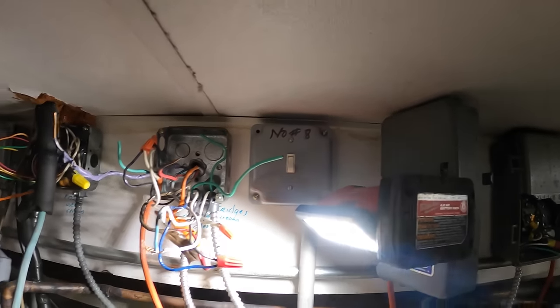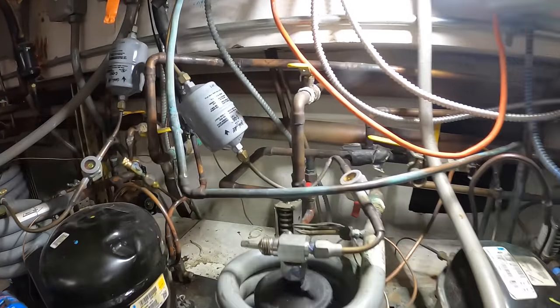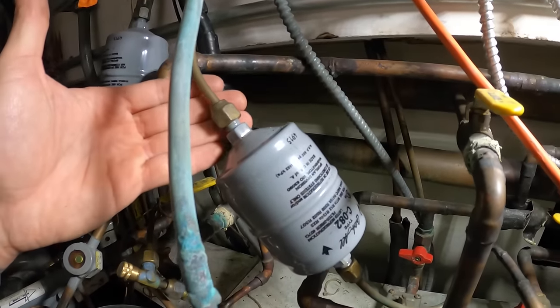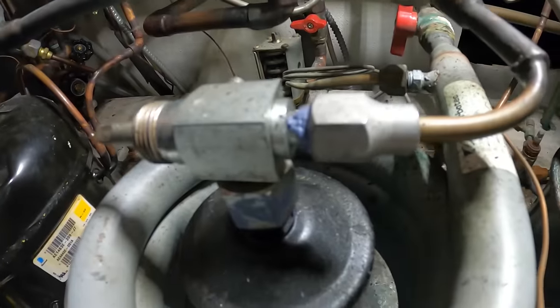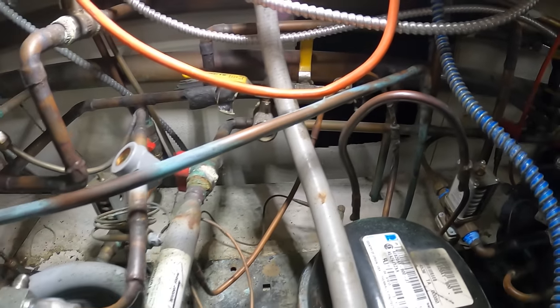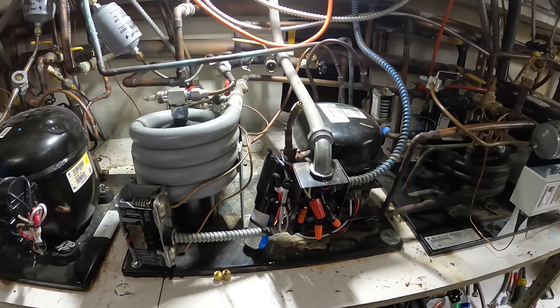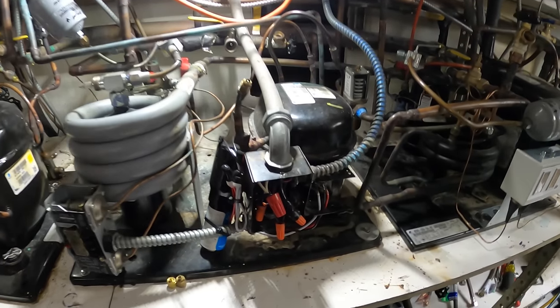Power switch is off. This thing is just a complete mess — look at this line right next to the electrical. Something is bound to go wrong here. We're mostly getting rid of any flares; these flares tend to leak. All that kind of stuff just creates problems, so the best bet is to braze all our connections and just junk this thing.